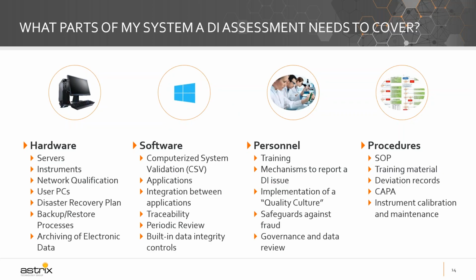So what parts of my system could a data integrity assessment cover? The reason why I put this slide together is to reinforce that data integrity is not only about software in your laboratory or network or the equipment you have. It's more than that. Data integrity sits over the four pillars of any system: the hardware, the software that is used, the personnel that operate in this environment, and the procedures that people follow. All of those combined need to be analyzed when you're looking at data integrity.